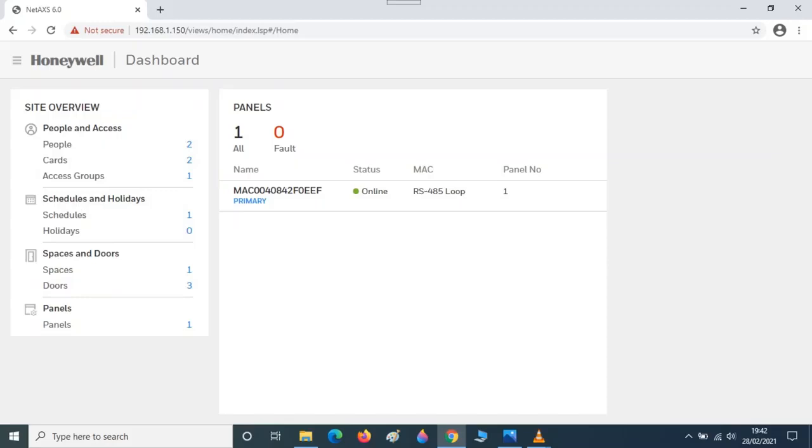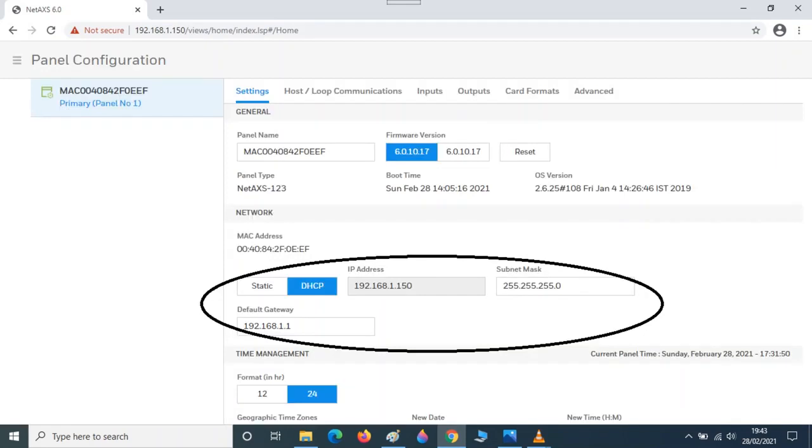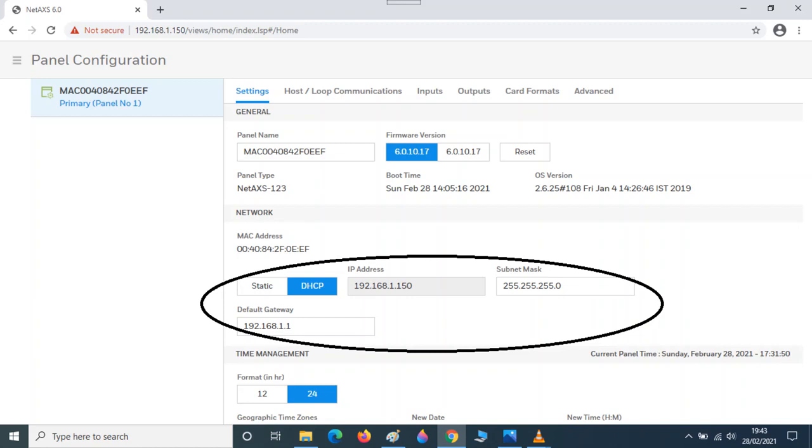The device can be left in the standard IP address if you like or you can change it. Simply go to the menu, Panel Configuration, Settings. And in there you can either give a static IP address or you can leave it as DHCP. I would suggest change it to static and give it a new IP address, or ask your client what their static IP address should be. Once you've inputted the new IP address, press Save.